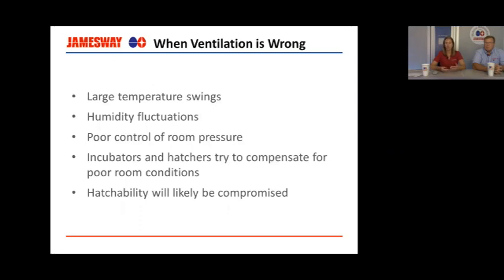We have poor control of room pressure. That means that the machines are getting an inconsistent quantity of air. So the incubators and hatchers, they have sophisticated control systems, so they're trying to compensate for the poor room conditions. Eventually they get to a point where they can't compensate well enough. Your hatch is compromised, your chick quality is compromised, things are not great.